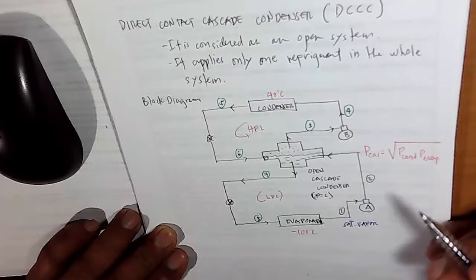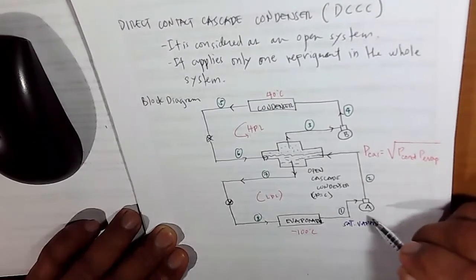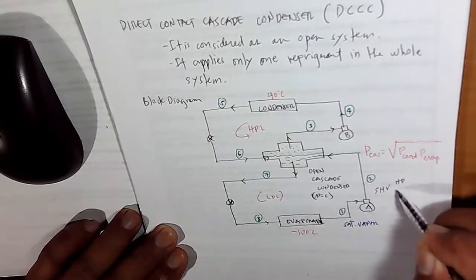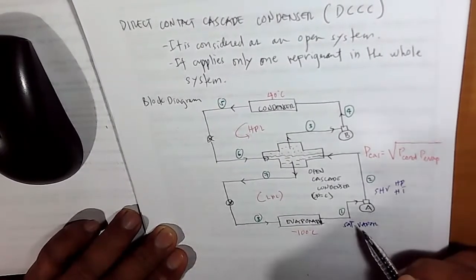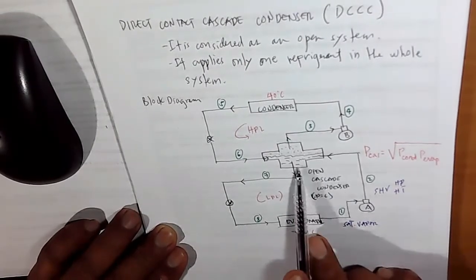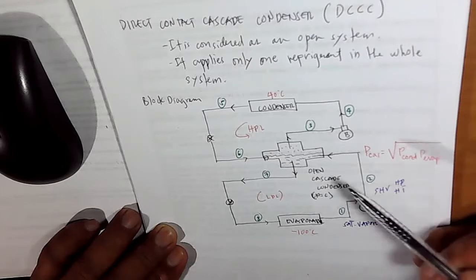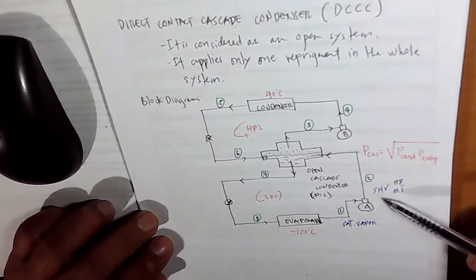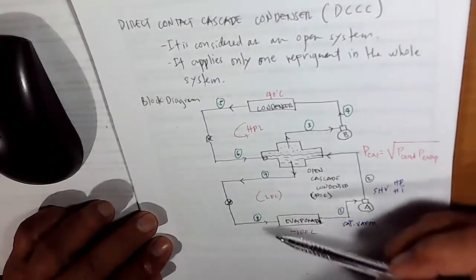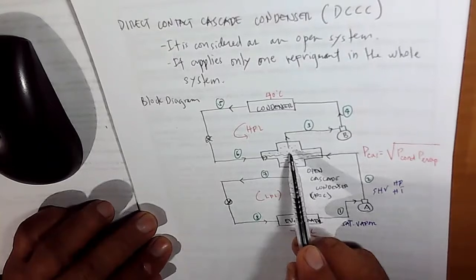That is the inlet requirement as it enters the compressor. When you compress it isentropically, it will change to superheated vapor — high pressure, high temperature — at the lower loop condition. It will now go to your cascade condenser, which is an open system, and mix with the refrigerant inside. Since the superheated vapor is submerged in the liquid, some of the superheated vapor will convert into liquid, and some of it is converted once again into saturated vapor.